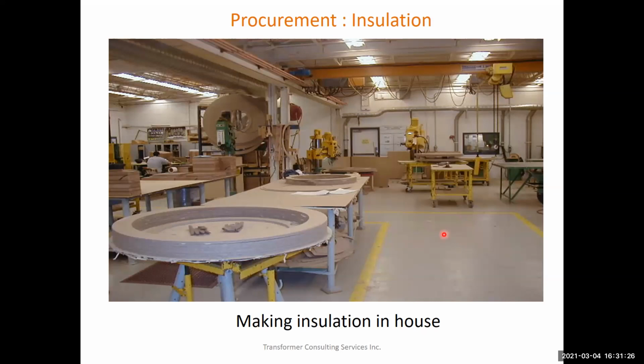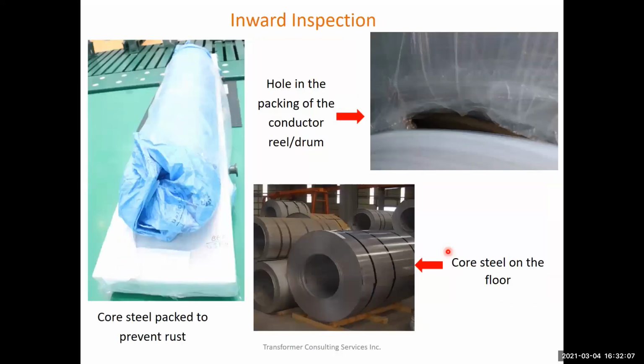Just imagine, look at the floor. If the floor is not clean, if this room is not climate controlled, for example not controlled for humidity, dust, or temperature, what's going to happen with this insulation? It's going to absorb the moisture and the dust, and it's going to stay inside the transformer. Now think about if the manufacturer is being aggressive in design because the quality of the factory has not improved. That means you are stressing your transformer. When you put the transformer into service, for a simple failure, the transformer can have a catastrophic failure.